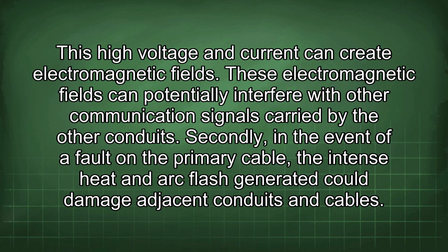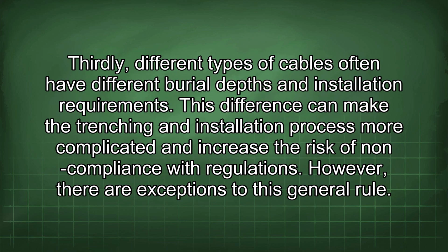Secondly, in the event of a fault on the primary cable, the intense heat and arc flash generated could damage adjacent conduits and cables. Thirdly, different types of cables often have different burial depths and installation requirements. This difference can make the trenching and installation process more complicated and increase the risk of non-compliance with regulations. However, there are exceptions to this general rule.